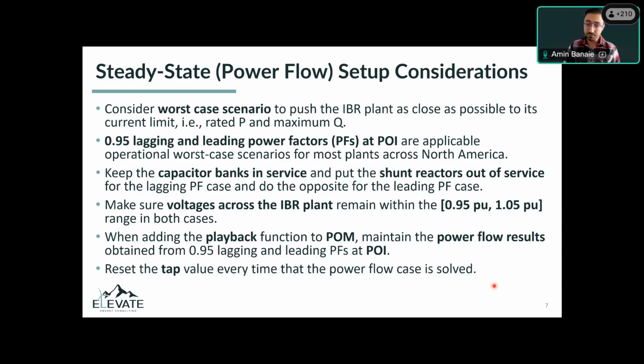And another consideration, which is very important to have in mind, is that for the lagging case, make sure to keep the cap banks in service if there is any cap bank in the plant, and set the shunt reactors out of service. And the reason for this is that you want your cases to be realistic as well.